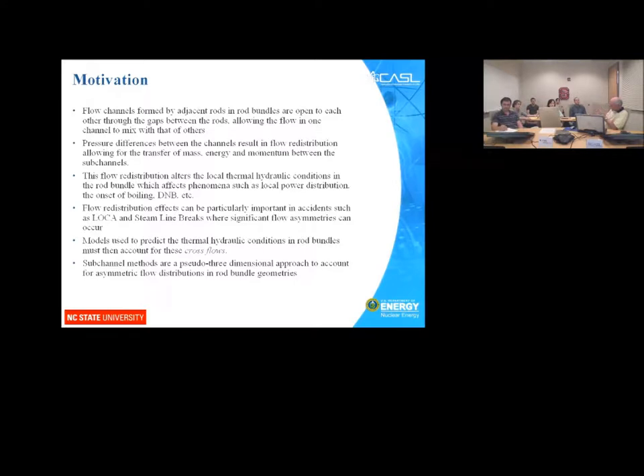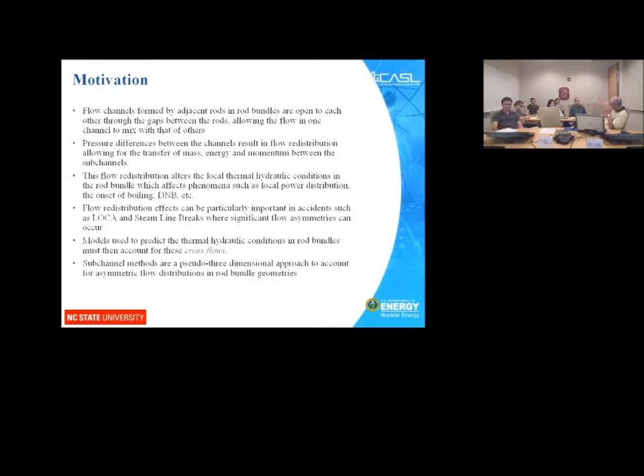While not necessarily within the CASL project at this point, at some point they are interested in accident situations such as loss of coolant accidents (LOCA) or steam line breaks. In these cases, you can have very large flow asymmetries — fluid moving from one part of the core to another as a consequence of a pipe break — and a large asymmetry in the pressure distribution radially across the core, giving you large flow mismatches.